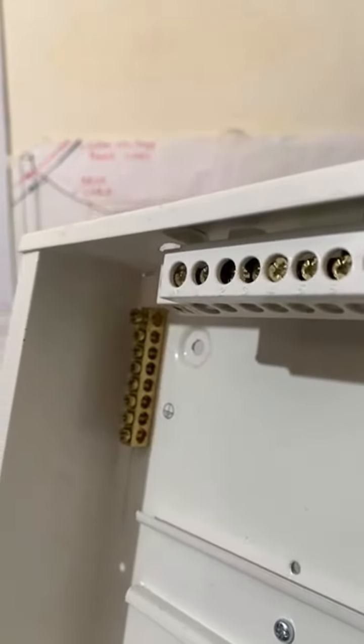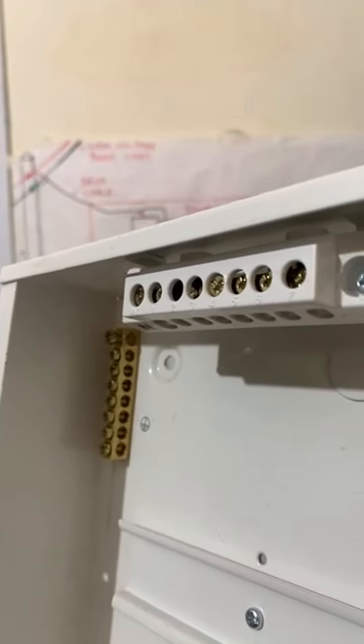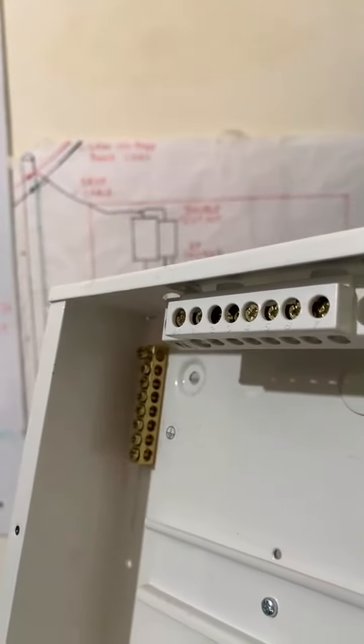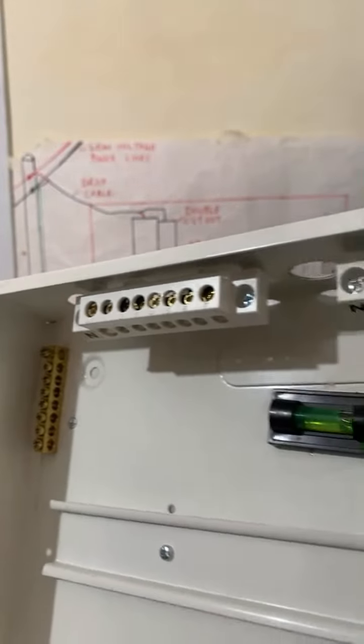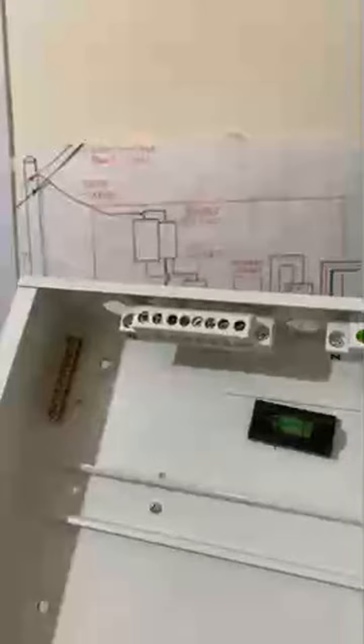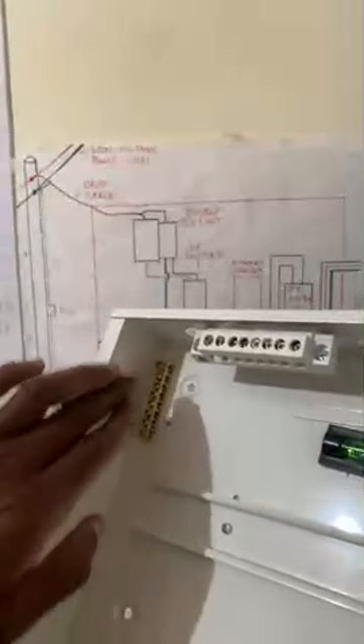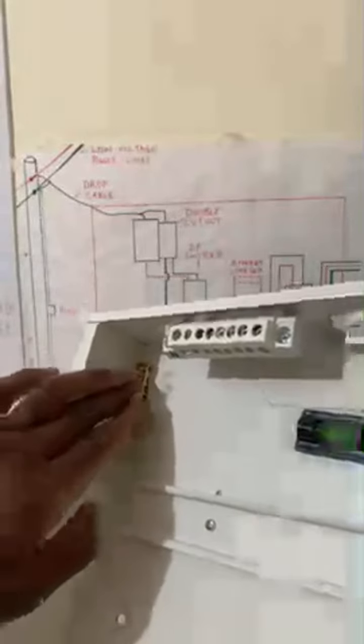That earth bar is purely made of copper material, and that copper material is also metallic. This is a metallic consumer unit. The purpose is to simply ensure that the earth connection is made perfect. So if I was doing that connection, I would still not rely on this one bar, do the connection there and leave it at that, and then start tapping earth connections for my circuits here.